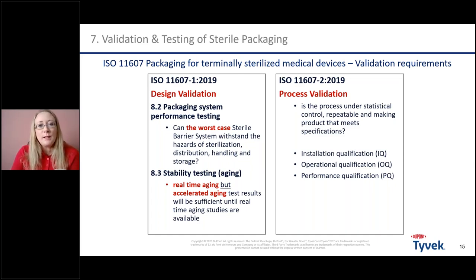Stability testing also needs to be done - real-time aging and accelerated aging. Accelerated aging results can already be used to commercialize the product, but real-time aging is necessary as well to claim the shelf life you need to claim. It's not shown here, but usability requirements and testing are also important to guarantee good handling of the packaging.